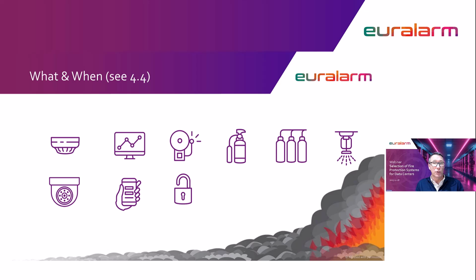But on the flip, could use of a portable fool the detection system into thinking the situation has rapidly got worse? They could, or arguably should, put the system in the manual mode of operation when they're taking control of the situation. It's rare to ever hear me say that. I am a stalwart behind keeping systems in their automatic mode, but in this case, that would make sense. And it needs that level of detail thought out, documented, written, and understood. And I'd say actually run through, get them to try it and ingrain it.